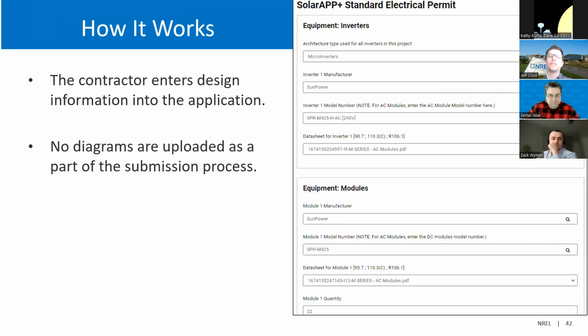As many of you know, oftentimes you'll get an incomplete plan, or it won't have all the information that you need to determine whether or not it's code compliant, but you still have to review the whole thing, then fill out all your corrections, and then send it back to the contractor. The SolarAPP product will not allow a contractor to submit a project without having a code compliant system, full stop. They can never send an incomplete application through SolarAPP that would otherwise not be able to verify code compliance. So here's an example of what the contractor is entering.